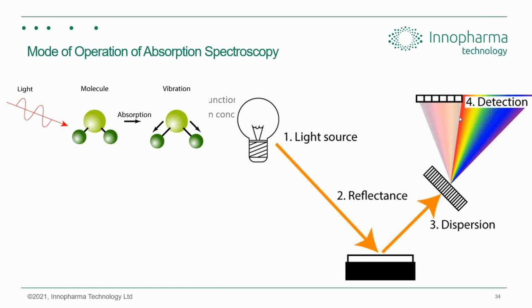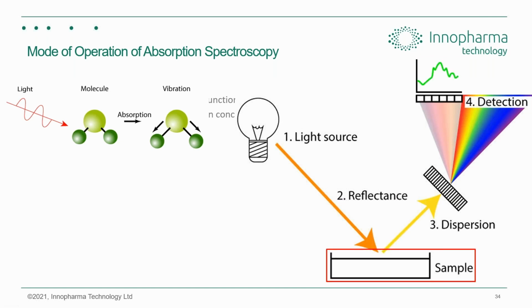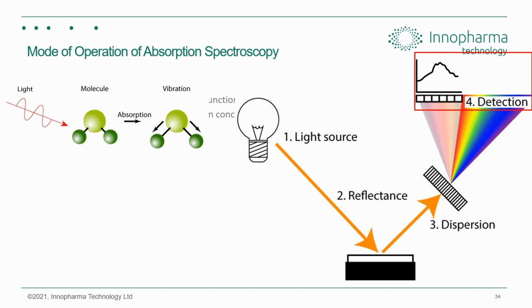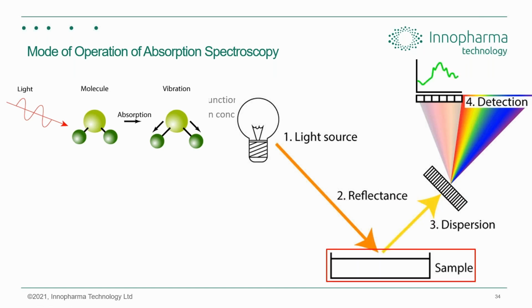So we can attach detectors to these. We can spread out separate detectors, have a linear detector array to tell us how much light is hitting, so the intensity of the light that's hitting each element of the array, and that tells us the wavelength of the light as well as the intensity. We can convert this into a spectrum by collecting the intensity observed at each of the different wavelengths, at each of the different detectors. And from there, we produce a spectrum. This is of the perfectly reflective surface, and we can compare that to a sample. By comparing light from a known reflectance standard to that of our unknown sample, we can measure the difference. And that tells us what's present, what's absorbing in the sample.